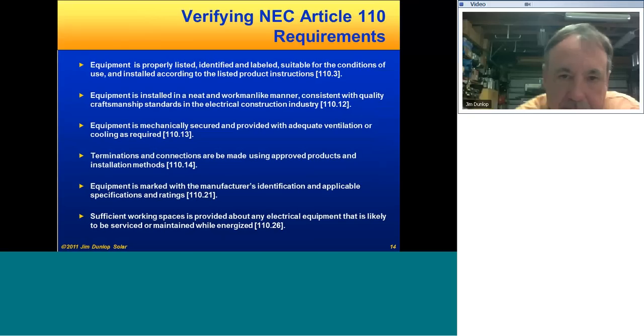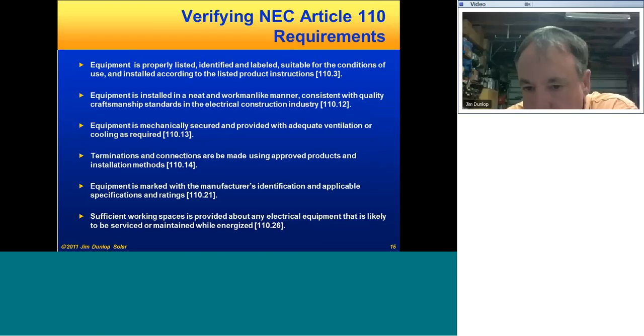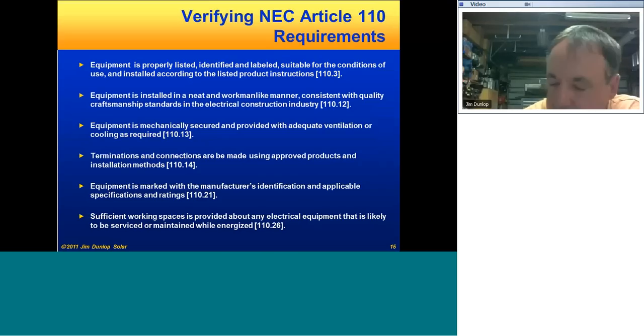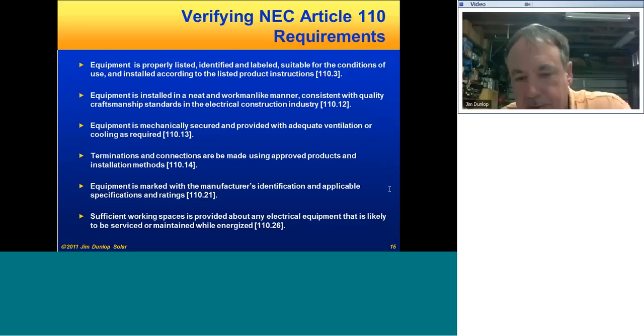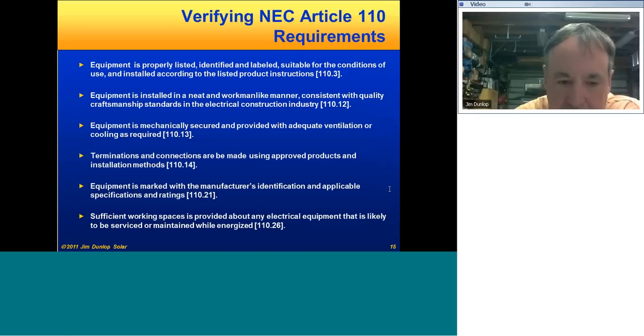Now, some of the things that can be verified in those visual inspections, obviously, the 110 requirements: looking to see the equipment's properly listed, labeled, identified, suitable for conditions of use, properly installed in accordance with the listed instructions, all done in a neat and workmanlike manner. Equipment's mechanically secure, provided with adequate ventilation and cooling, especially for inverters, arrays, and so forth. Terminations made using approved products and methods, including torques, as I mentioned. You've got equipment that's all marked properly with the manufacturer's labeling. Sufficient workspaces are allowed about all equipment. That's kind of a real problem with retrofits, trying to jam an extra PV inverter or two into places where they probably don't fit. But any of that stuff that has to be worked on energized has to have certain working clearances, and any electrical equipment has to be installed with certain space about it. So take a look at those requirements in 110.26.